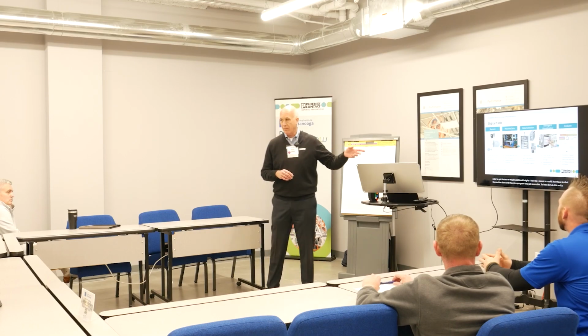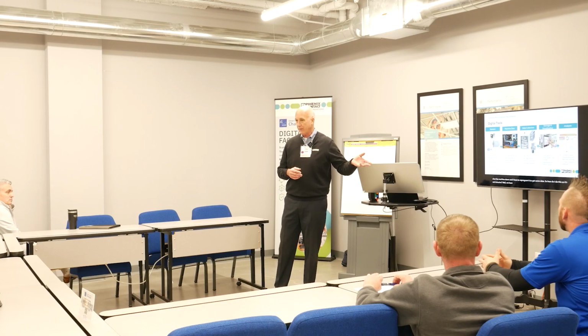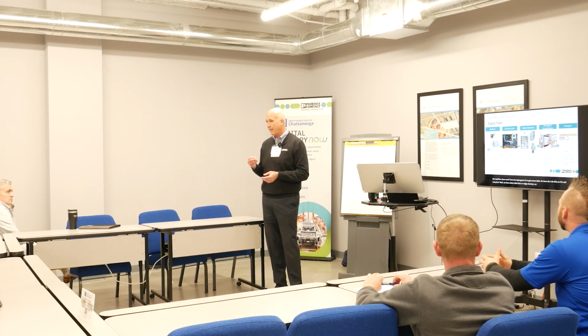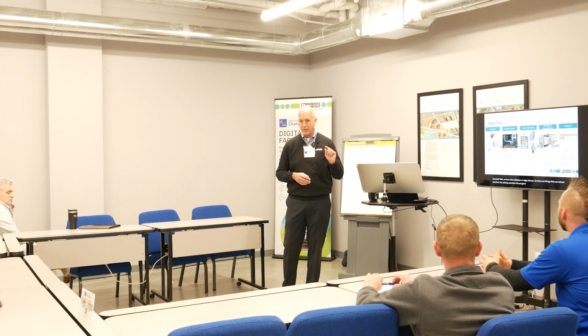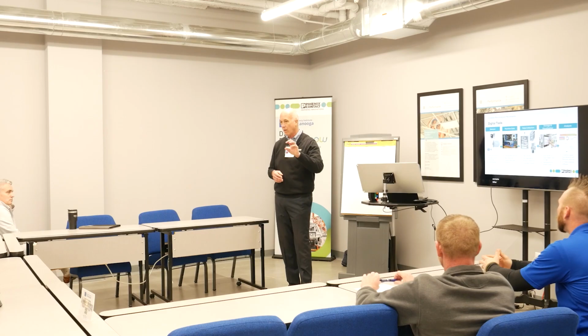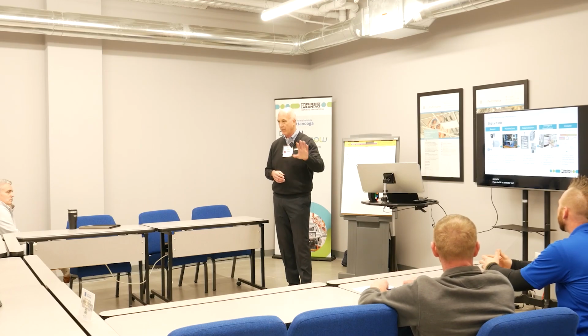Well, we call these data collection or edge devices. These are things that can extract data from the existing operation. The program resides in the edge device and it simply connects via Ethernet IP or Profinet, some protocol, and pulls out data from the machine without disrupting the production operations.